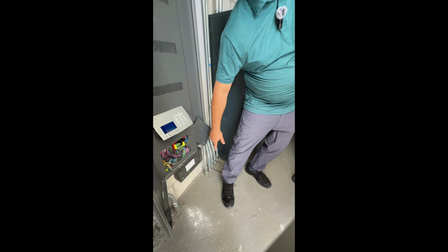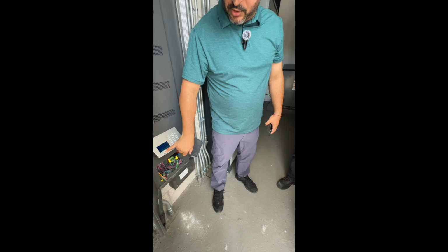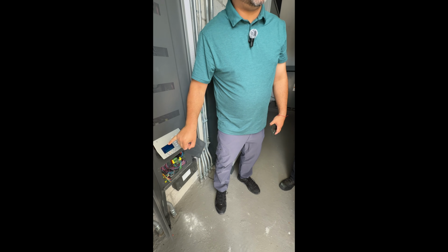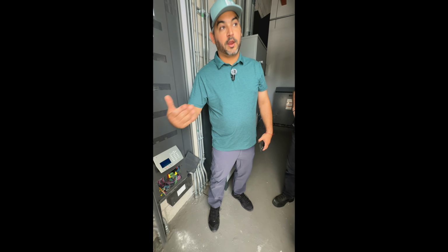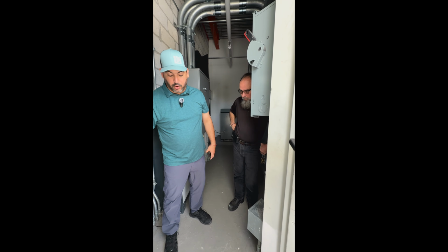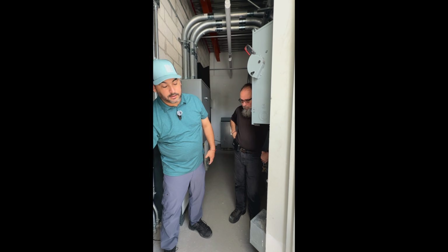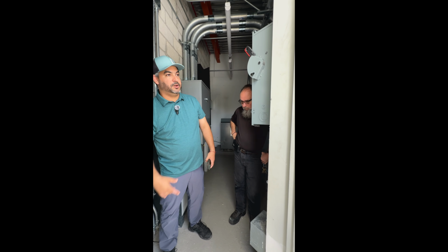And when we say time clock events, we're only talking about the sunset and sunrise. Yes. So there are schedules programmed in this lighting control panel that are working, and there is no warning. The OK is just that it's getting signal information. That photo cell is saying, hey, stay open, don't close because there is enough light.